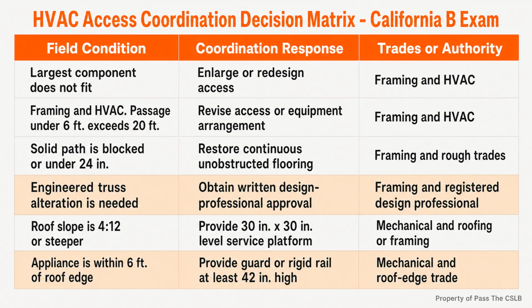Follow the path. If headroom is less than 6 feet, is the center line distance no more than 20 feet? Is the flooring continuous, solid, and at least 24 inches wide? Is the route still unobstructed after ducts, pipes, wiring, braces, and insulation are installed? Arrive at the appliance. Is there a level 30 by 30 platform at the actual service side? Can the service panel open? Can expected components be handled without stepping into an unsupported area?